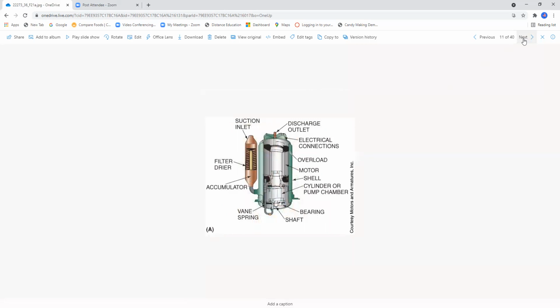And here I believe this appears to be a rotary compressor. I'll verify that. Rotary compressors are used a lot; I've seen them in mini splits and in window air conditioners. They do a very, very good job. They're very simple and they hold up a long time. So this rotary compressor is going to be found on page 1073 of your textbook under figure 36.21. Basically these are your different components: your vane spring, your shaft, your bearing, your cylinder or pump chamber, the shell, of course, that's surrounded here.